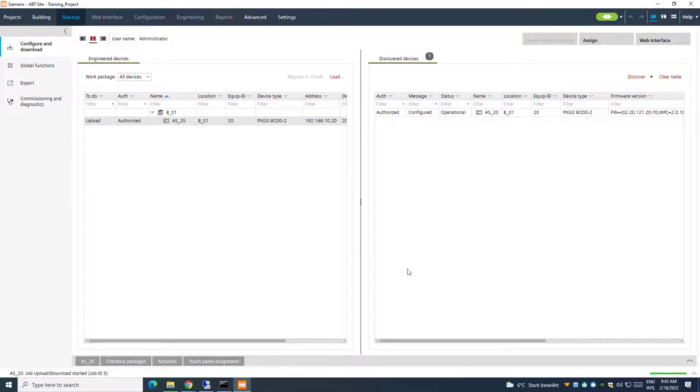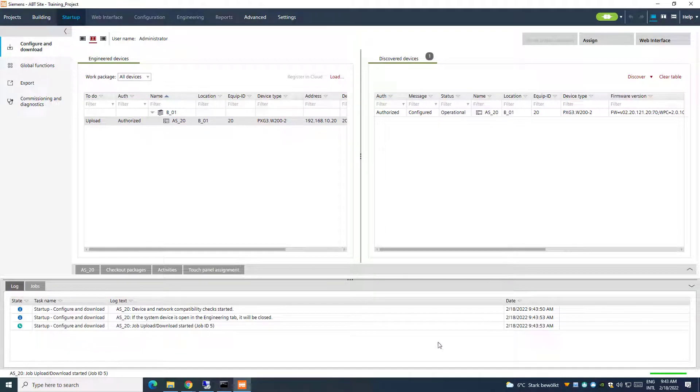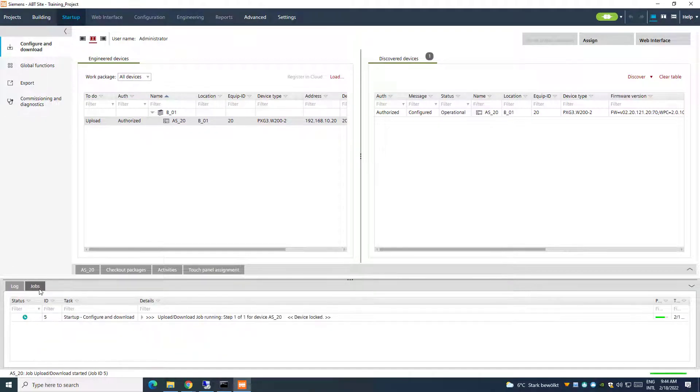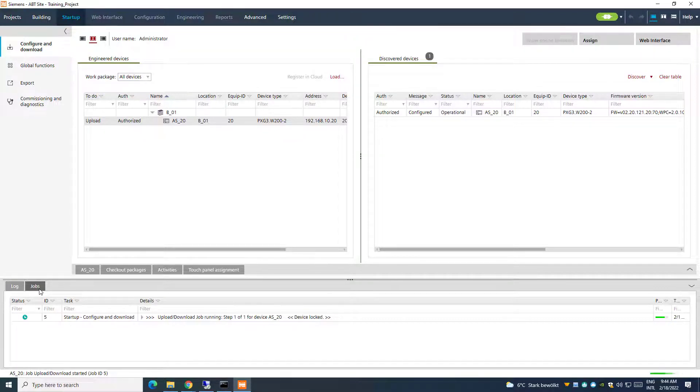With this procedure, the system will first upload the online changes into the offline mode, without overwriting the offline changes, and then will directly download the new offline configuration into the device, merging all the changes.